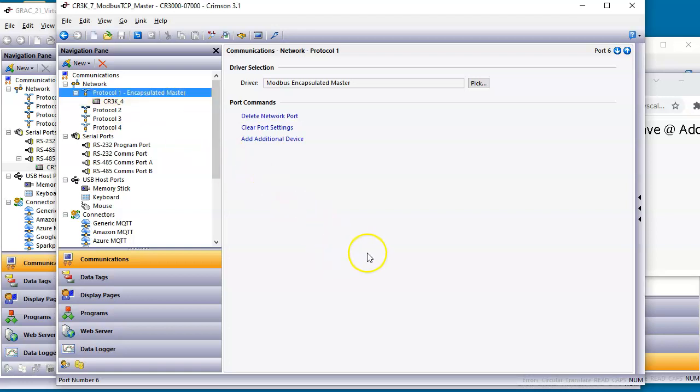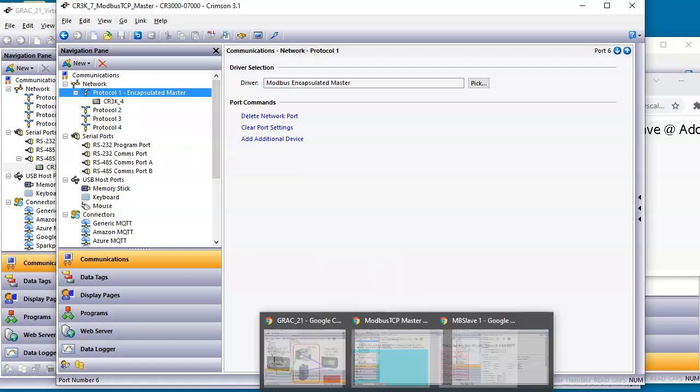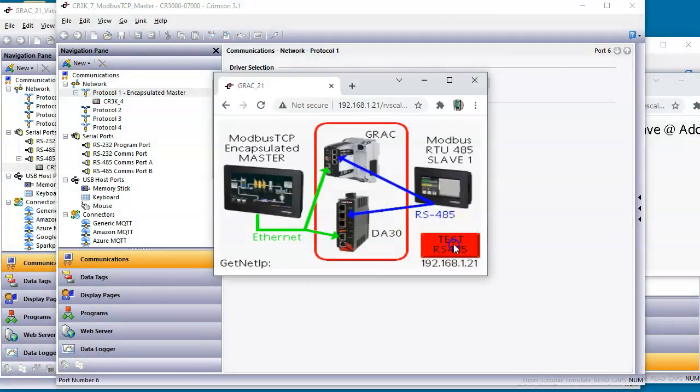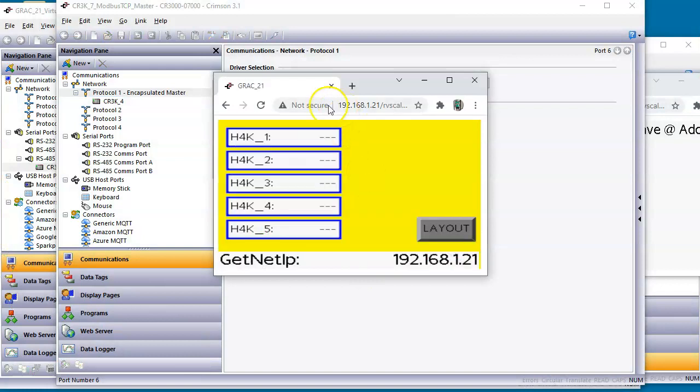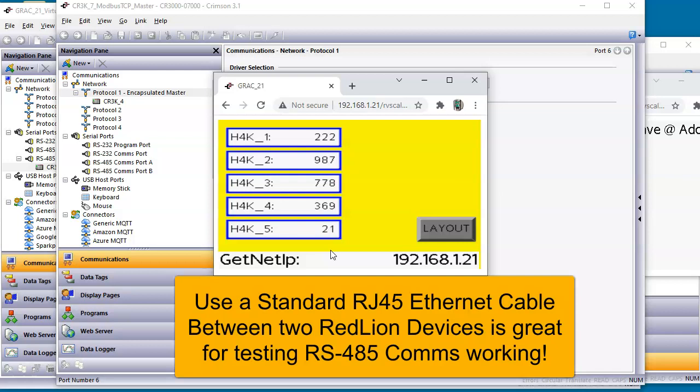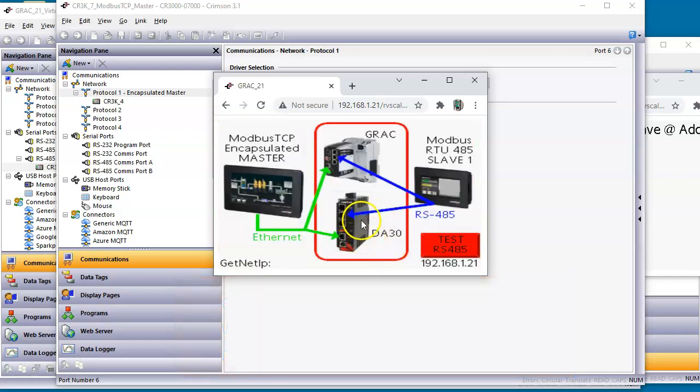Also, one thing I'll tell you that I really do all the time between two RedLion products, whenever I'm testing 485 ports on RedLion devices, I typically will just take a standard Ethernet cable and plug it into the RJ45 jacks and not have to cut any wires or anything. And it pins out just right and lets it connect right up. So you can see, I can test my comms. That makes for me a way to validate that the RS-485 port is working correctly. Anyway, I just thought I'd show off that cool demo. You could do the same thing with the DA30, but pretty cool. And a way to use the RedLion product to basically do serial to TCP comms. So anyway, thanks a lot. Have a great day.